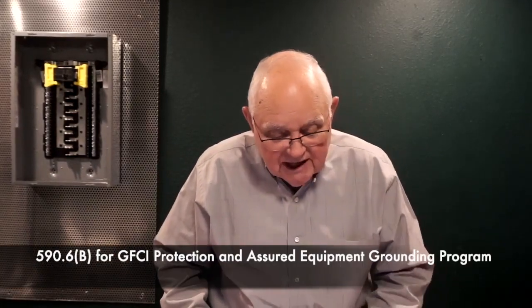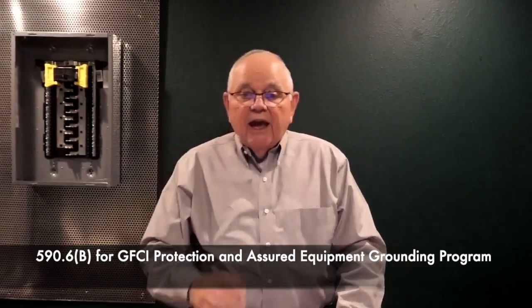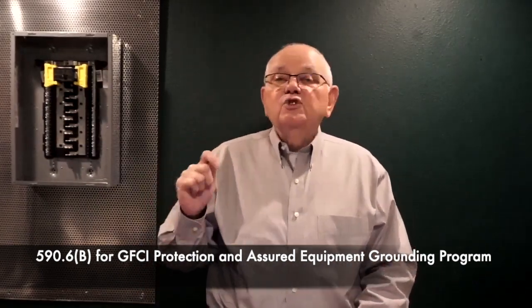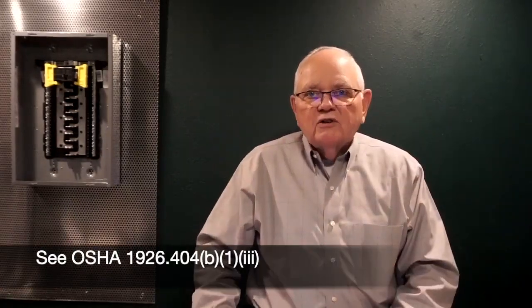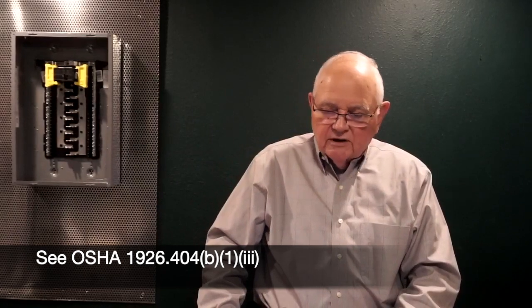Also, you want to take a look at your requirements in 590.6(B) for GFCI protection, and the alternative, which is to use the Assured Equipment Grounding Conductor Program. The Assured Equipment Grounding Conductor Program is covered in the NEC, as I mentioned in 590.6(B), where we are now. And it's also covered in OSHA. So OSHA is, of course, our real driving force for the Assured Equipment Grounding Conductor programs.